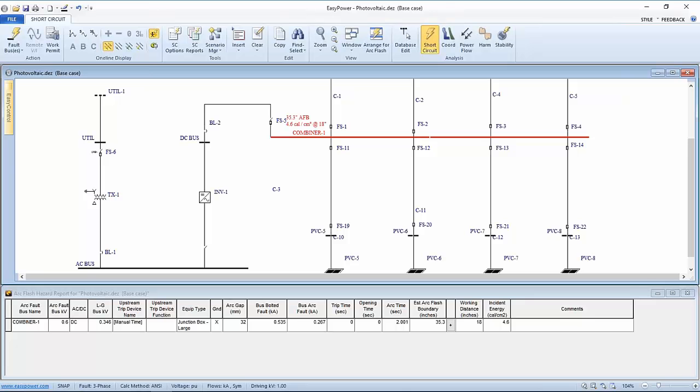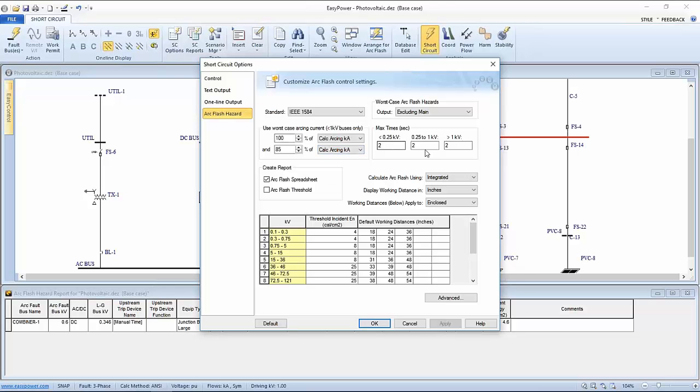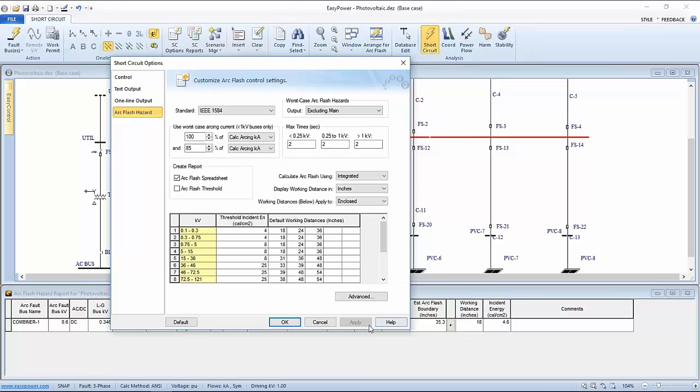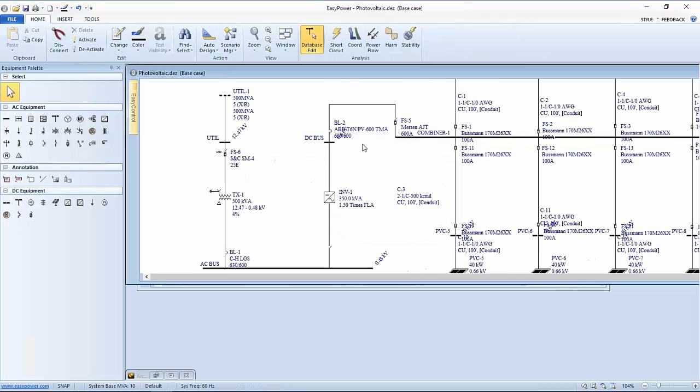Again, when we go back on the DC side, this is controlled by the maximum current which is set up under the short circuit. That's a good point. Where are we going here? So this is a 2-second time that's being limited for these calculations. If we decide that, well, in reality, this current won't be as dangerous as this 4 calorie level we're predicting, one alternative to dealing with that is going back to this bus.